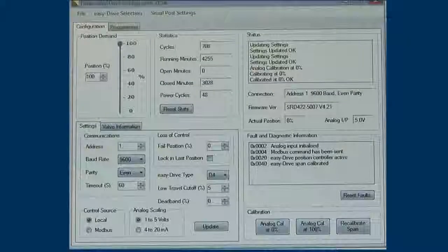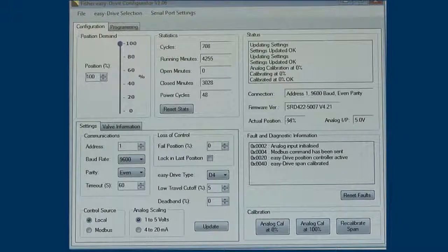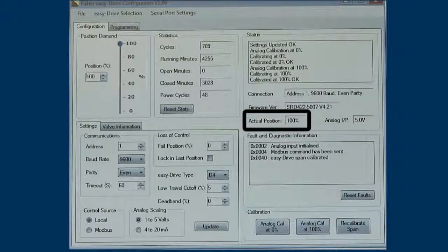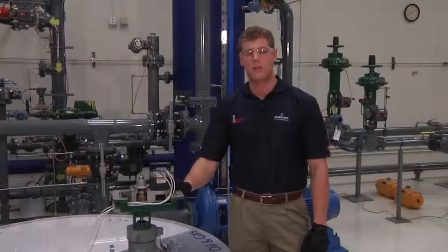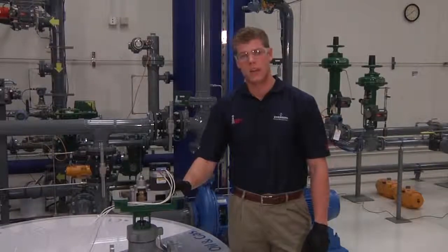Now using your analog signal device, apply a 20 milliamp signal to the actuator. Once the signal has been applied, click Analog Cal at 100%. And the valve should be fully open and the actuator position should read 100%. If the position is accurate, you have successfully calibrated your Easy Drive actuator and it is ready to be commissioned in the field.